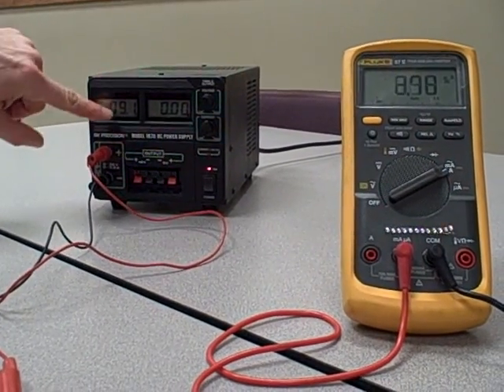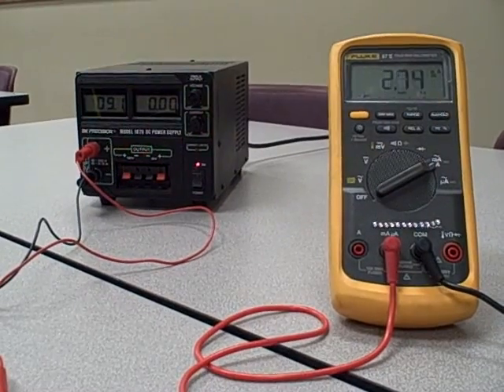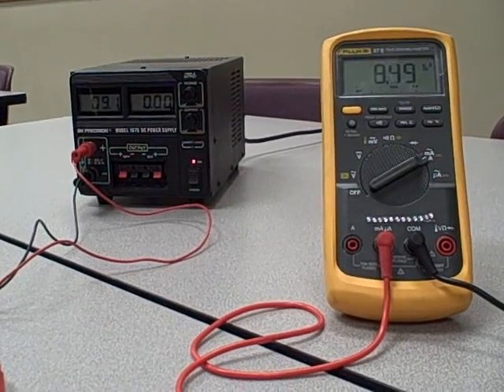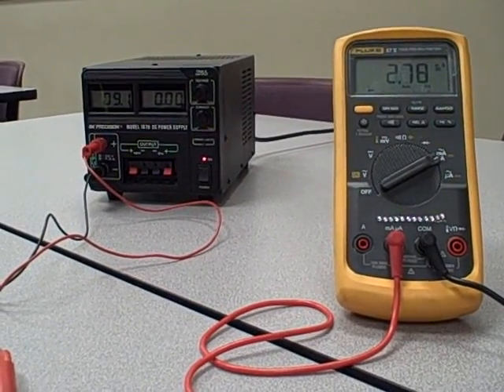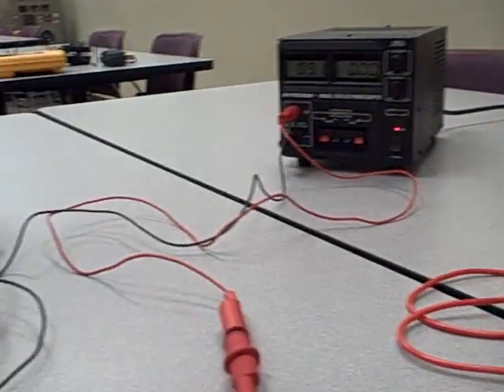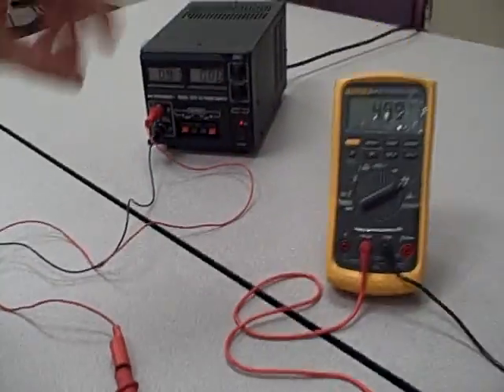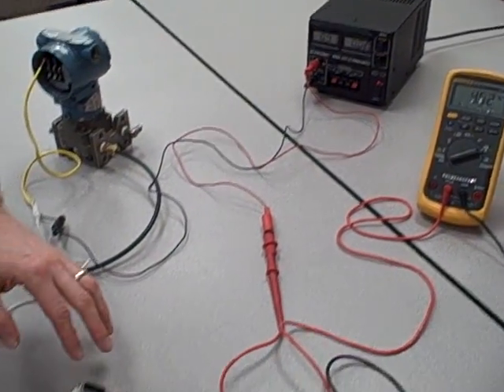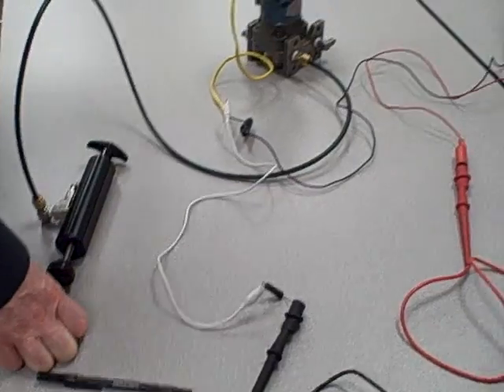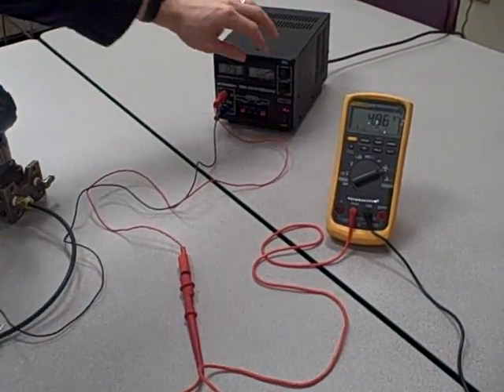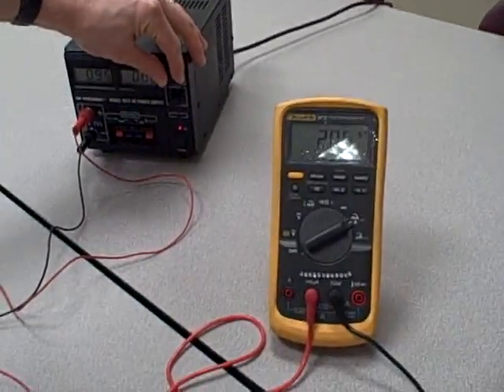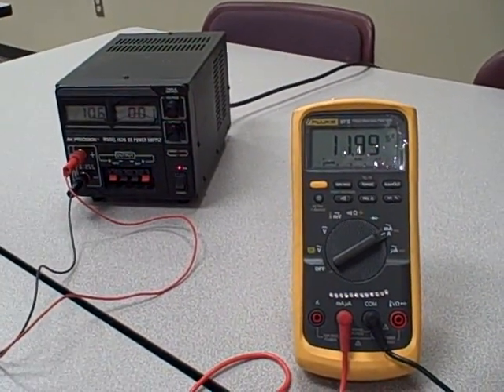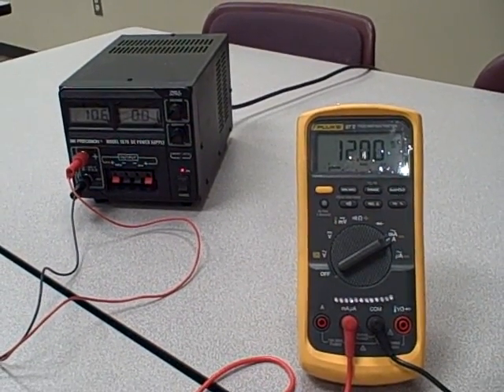At this point I'm about 9 volts, and you can see my current has dropped well below 12 milliamps. At this point, I am not applying enough voltage to the transmitter terminals for it to successfully operate. And this microcomputer inside the transmitter is having problems. And that's why we see the current bounce up and down. The microcontroller is trying to power up. When it does so, it drops more voltage through this resistor. It loses operating voltage and powers back down. So we have kind of a weird cycling action right now. If I turn the power supply voltage up high enough, that behavior stops. Here we can see it stopped at about 10.6 volts. And now the transmitter is able to function properly.